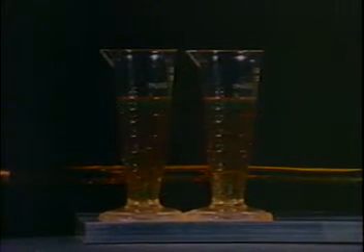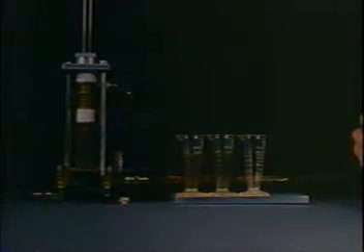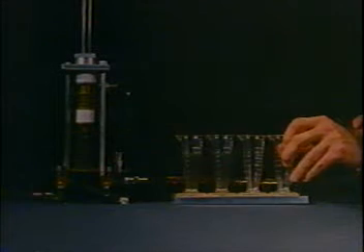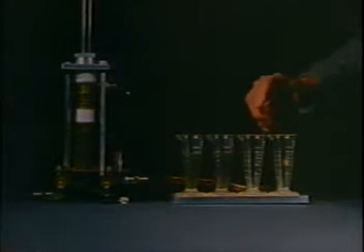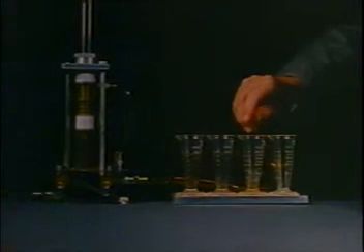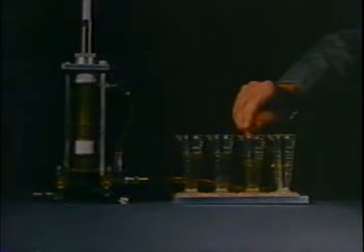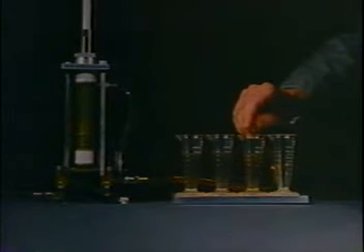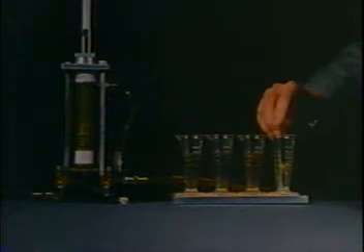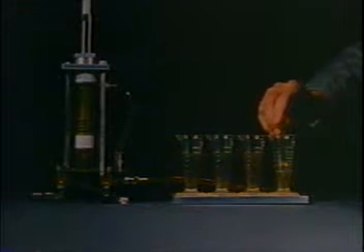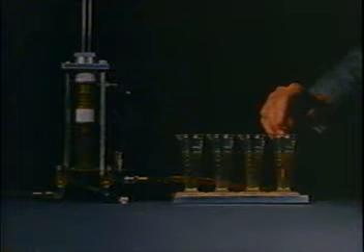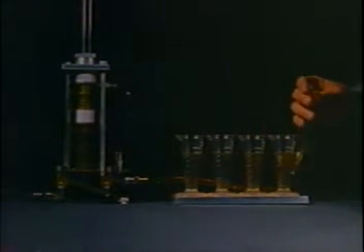The volume of liquid pumped forward on a complete cycle is called the displacement of the pump and is determined by the pump's dimensions. The ability to pump an equal predetermined volume of fluid on each cycle, the feature which is referred to as positive displacement, is made possible by the effectiveness of liquid seals within this piston pump, which prevent internal leakage and recirculation of liquid between the high-pressure outlet and low-pressure inlet, assuring delivery of the full volume for which the pump was designed.